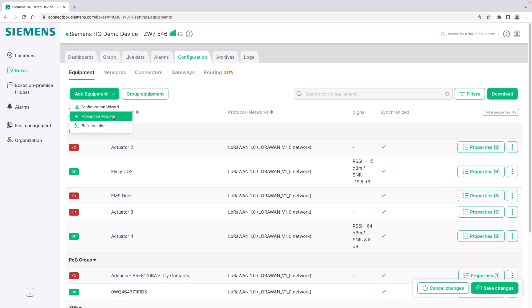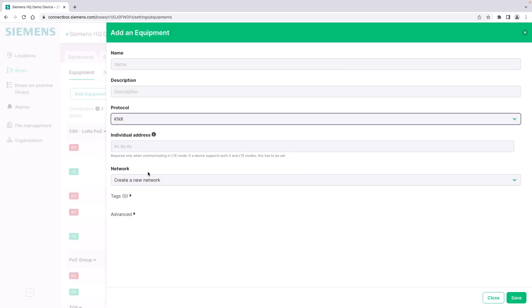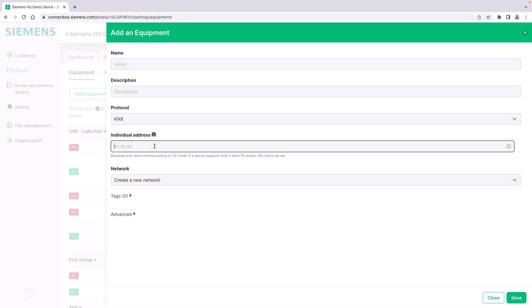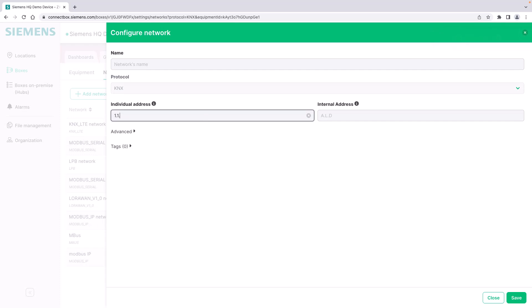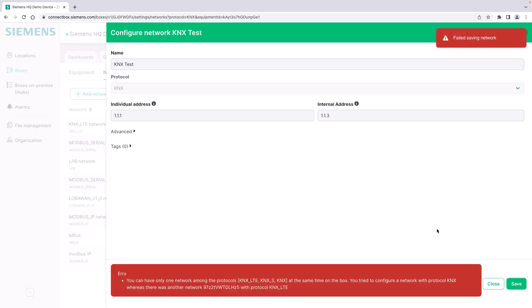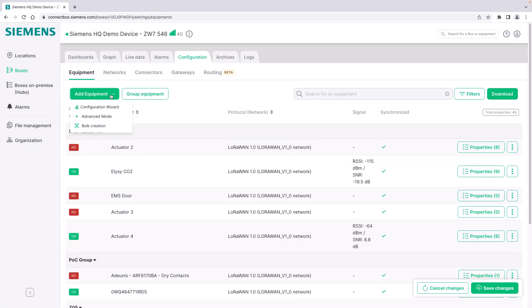Another functionality for adding devices is via the advanced mode. In the advanced mode you can choose the protocol manually, for example KNX. You can define for example the individual address of the device that you would like to add, you give it a name and you will get to the next step configuring the network. As we didn't add a KNX S-mode network before we do it here. And you see here whenever I'm trying to do something that I'm not allowed to, the box and the configuration web interface is already telling me what is the problem. In this case I already have a KNX LTE network which is a subcategory of the KNX protocols and the configuration wizard here is telling me that I cannot have both of those protocols on the box. So first I would need to delete the KNX LTE network.